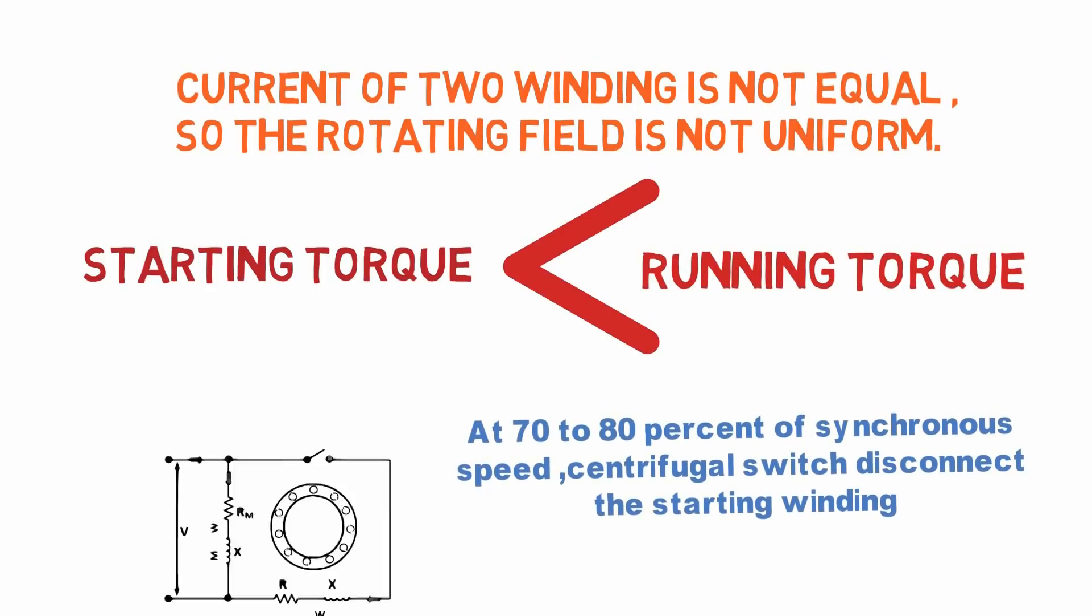After getting 70 to 80 percent of synchronous speed, the starting or auxiliary winding is disconnected from the supply by using this centrifugal switch.